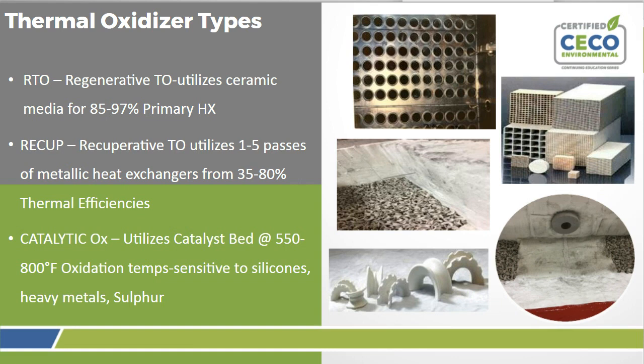The recuperative oxidizers use a shell and tube or plate and frame heat exchanger. The upper left shows a shell and tube. I think those are 1.5 inch round stainless steel tubes. Those have expansion joints with the various bundles to prevent leakage, to get you the high destruction efficiency. You will get some expansion and contraction. If not done right, you can get some leakage, and that will deteriorate your VOC destruction over time. So you want to definitely pick a good system that has good expansion and good leakage control and good welding on that.